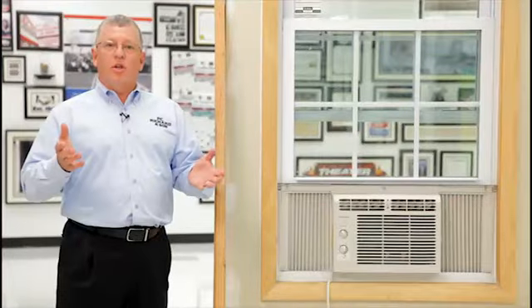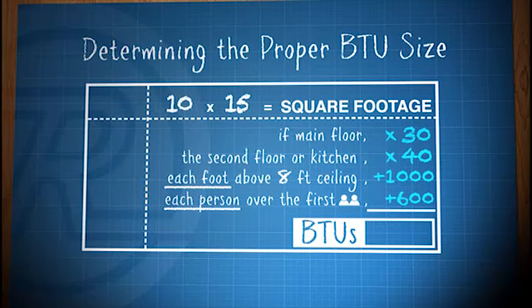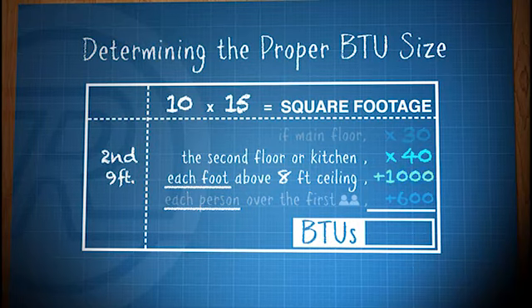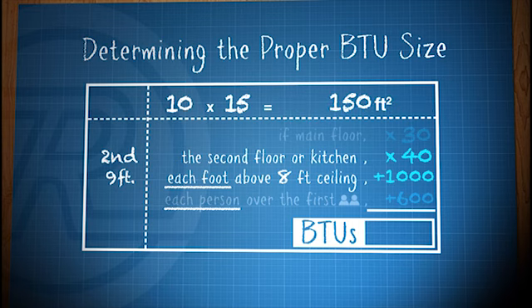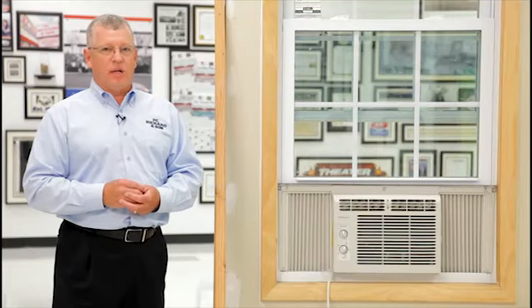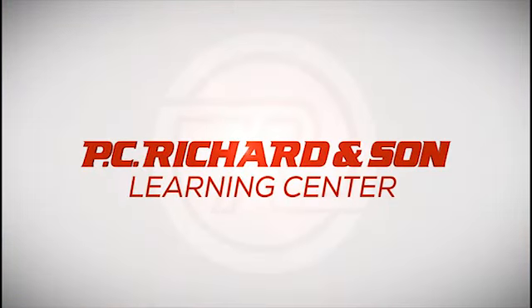For this example, we're going to use a room that's 10 by 15. It happens to be on the second floor with a 9-foot ceiling. A 10 by 15 room equals 150 square feet. It's on the second floor, therefore we'll multiply it by 40, giving us 6,000 BTUs. We mentioned that the ceiling height was 9-foot, so we want to add an additional 1,000 BTUs for a total of 7,000 BTUs.